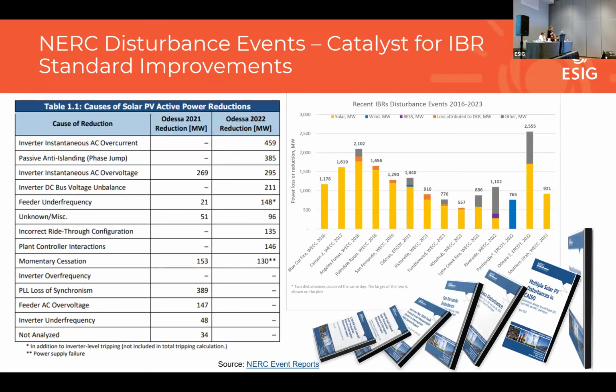And I think where the need for this unified interconnection requirements is obvious is the NERC disturbance events that have been happening, or at least been reported, since 2016. What you see on the chart here, these events in yellow, this is solar tripping for a normally cleared fault, where solar tripped unexpectedly on multiple resources. And the last event happened in 2023 in Utah, and 2 big events in Odessa, Texas, and that's what you see on the left-hand side, the table from one of the Odessa events.